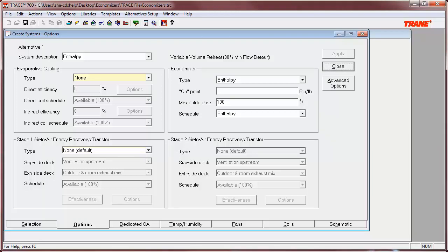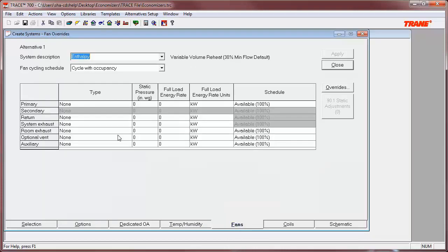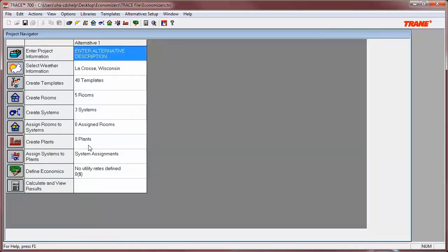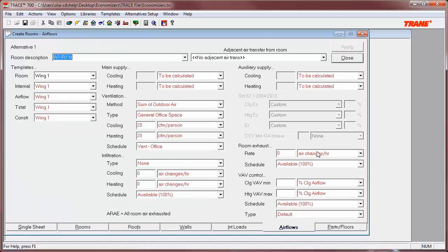Regarding the requirement to relieve building pressure to prevent over-pressurization: since TRACE functions on the premise of neutral pressure in each room and thus throughout the building, this pressure relief is inherent. However, if the system being modeled requires the use of relief fans, these fans will need to be modeled on the fans tab of Create Systems, using either the system exhaust fan if all exhaust is leaving the building through the system, or via the room exhaust fan if exhausting air via the room exhaust field on the air flows tab of Create Rooms.